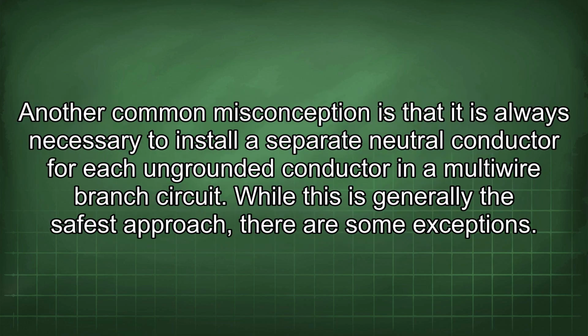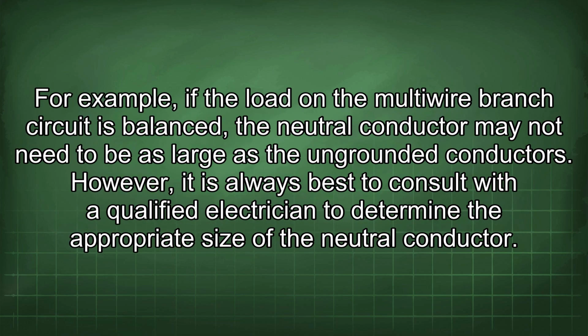Another common misconception is that it is always necessary to install a separate neutral conductor for each ungrounded conductor in a multi-wire branch circuit. While this is generally the safest approach, there are some exceptions. For example, if the load on the multi-wire branch circuit is balanced, the neutral conductor may not need to be as large as the ungrounded conductors. However, it is always best to consult with a qualified electrician to determine the appropriate size of the neutral conductor.